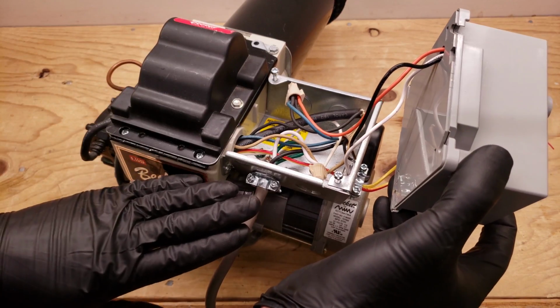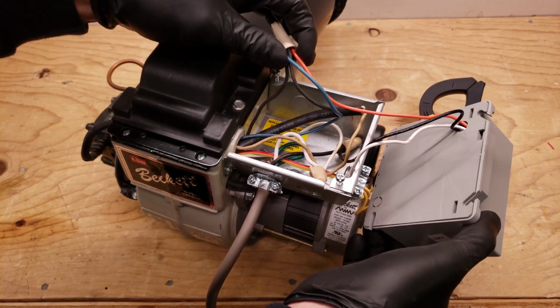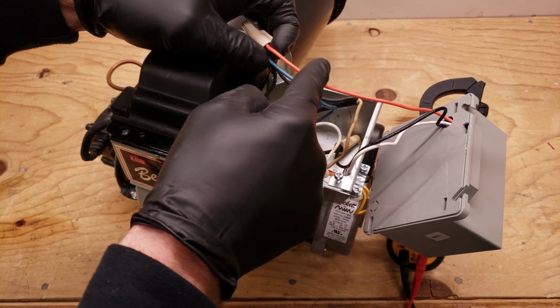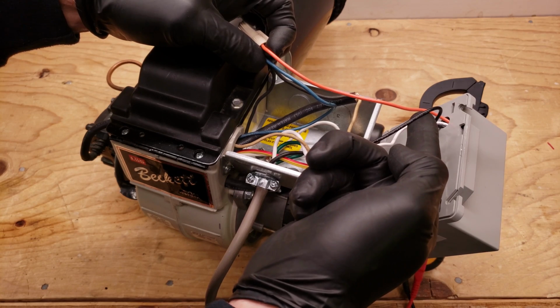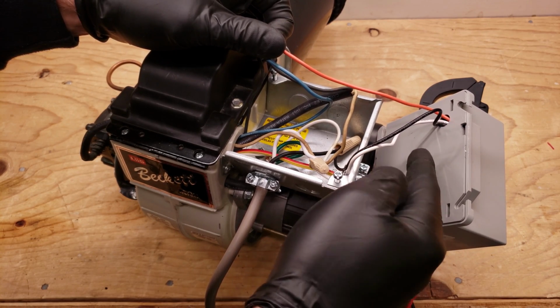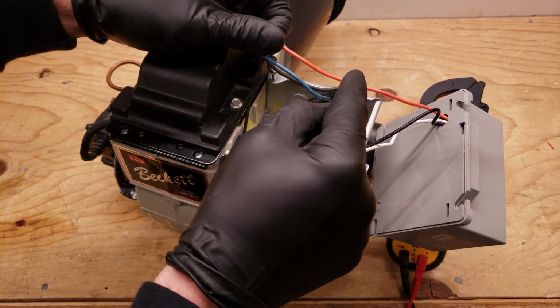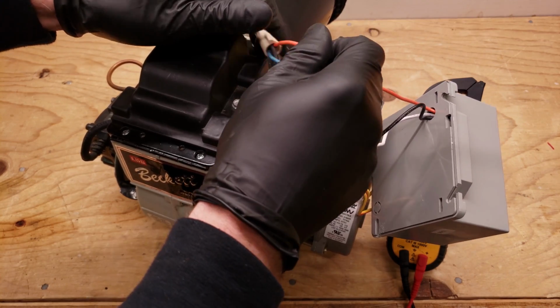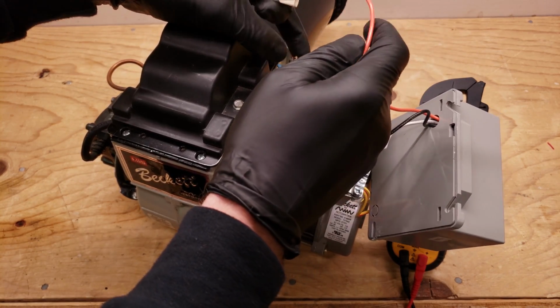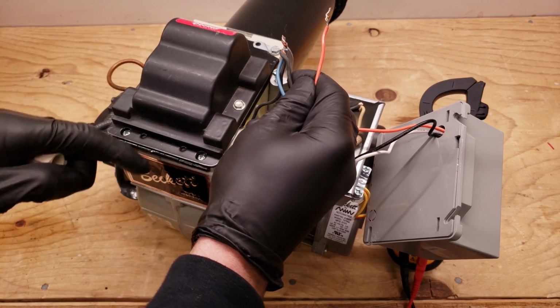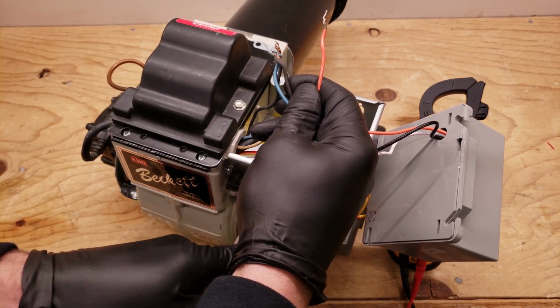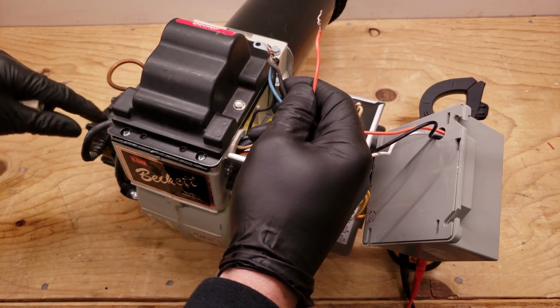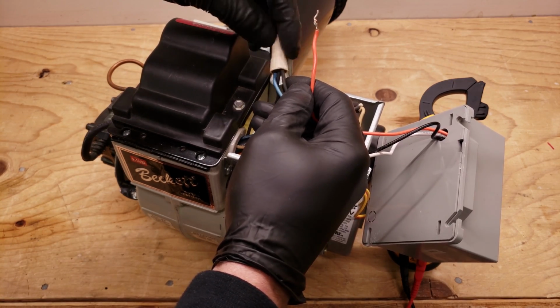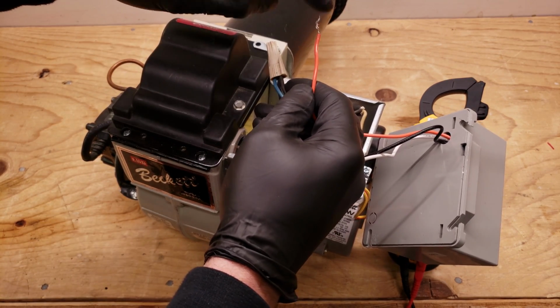And right now we have the power off, by the way. And you see this orange wire, that's the output wire. This is the 120 volts into the primary control and the common for the primary control. And this orange is 120 volts out. So remember that this orange is sending 120 volts to these three wires, the motor, the transformer, and the solenoid. So what we need to do is we're going to take an output reading on this right here.